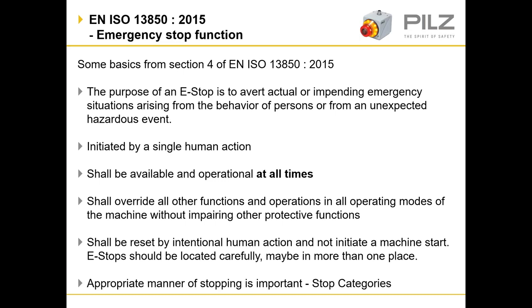Emergency stops shall be reset by intentional human action and shall not initiate a machine start. Emergency stops should be located carefully, maybe in more than one place. Once the emergency stop is twisted and released, this cannot be automatic — this must require a machine reset and then a machine start signal following the reset. Emergency stop actuation needs to be investigated as this should indicate an emergency situation. Resets need to be in sight of where the e-stop was actuated to ensure it is safe to reset and restart the machine.